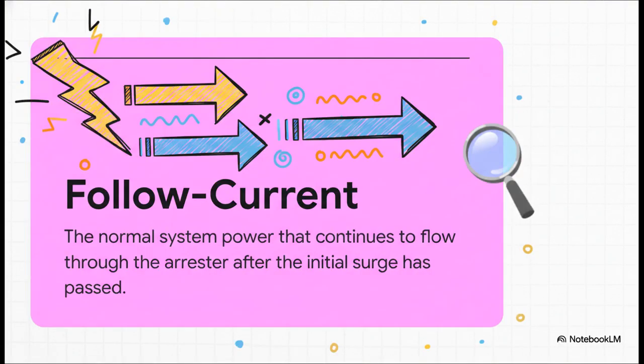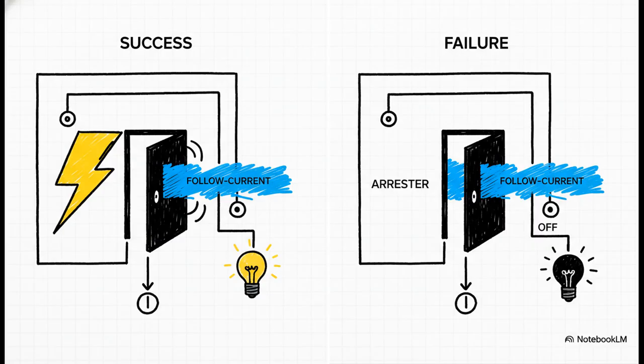All right, next up is a tricky little problem the arrestor can actually cause for itself. It's called follow current. See, after the lightning surge is gone, the grid's normal power is still there. And since the arrestor just opened up a nice path to the ground, that normal system power wants to do exactly what the lightning did and follow it right down. This is so critical. The arrestor has to be able to slam the door shut on that follow current instantly. Because if it doesn't, the grid's own safety systems will see it as a short circuit, a fault, and they'll trip a breaker, causing a power outage. So, a great arrestor doesn't just save the equipment, it does it without causing a blackout.